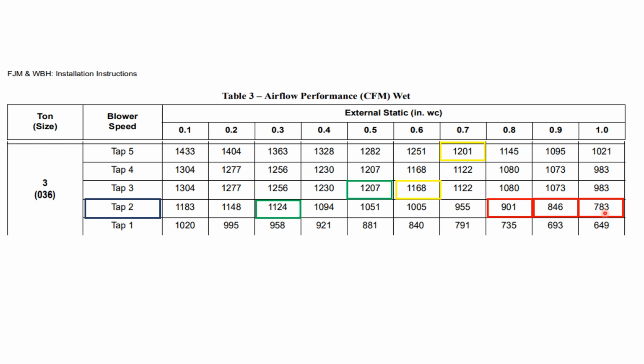Now, that's what I want to look at. I have to have that much airflow coming across that coil to produce 36,000 BTUs so my house gets taken care of. So I have to have 1200 CFM. This is going to tell me what I have.